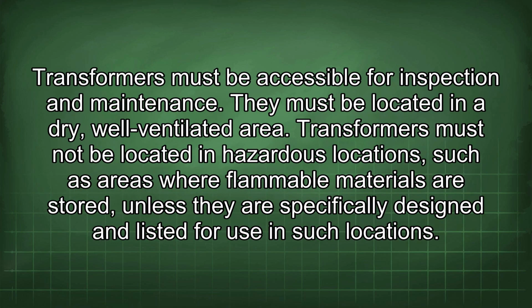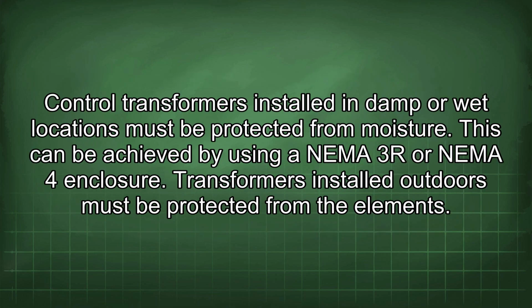Transformers must be accessible for inspection and maintenance. They must be located in a dry, well-ventilated area. Transformers must not be located in hazardous locations, such as areas where flammable materials are stored, unless they are specifically designed and listed for use in such locations. Control transformers installed in damp or wet locations must be protected from moisture. This can be achieved by using a NEMA 3R or NEMA 4 enclosure.